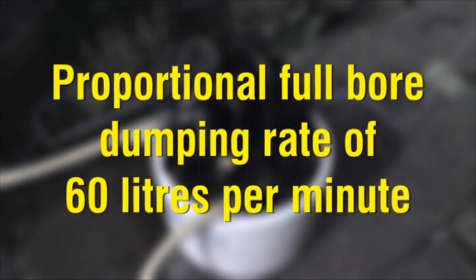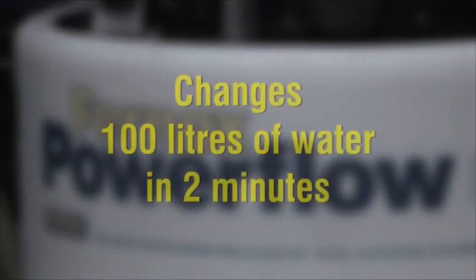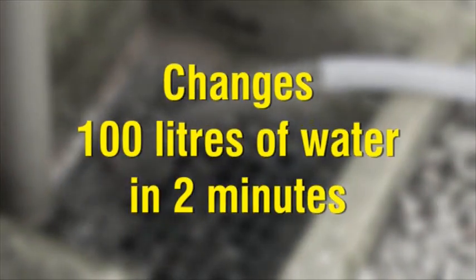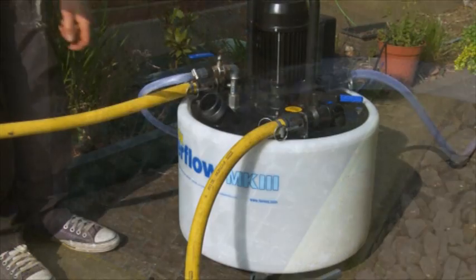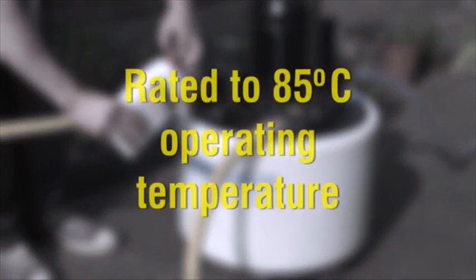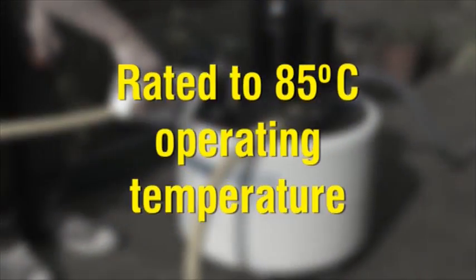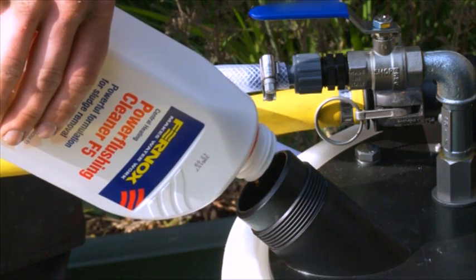A proportional full-bore dump rate of up to 60 litres per minute enables the water in a typical 10-radiator or 100-litre system to be changed in less than 2 minutes, significantly reducing time on site. The Powerflow is rated to 85 degrees Celsius operating temperature, which when used with a Fernox cleaner, even baked-on corrosion and limescale can be removed faster than with any other machine.